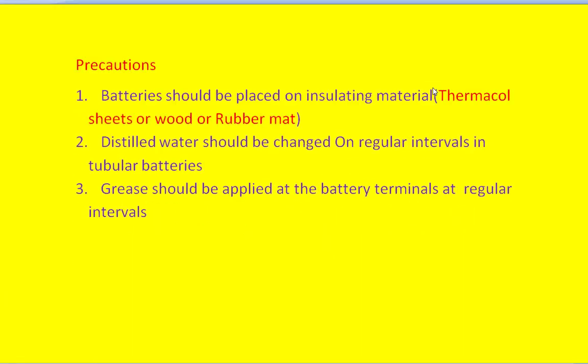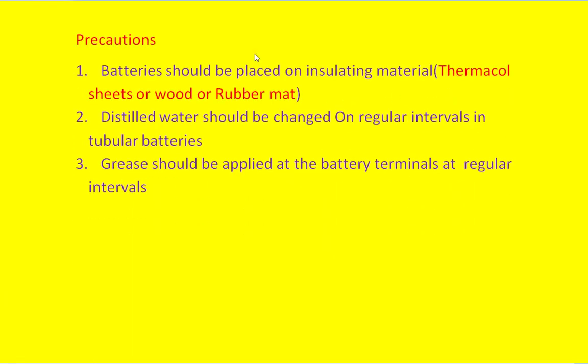Next, coming to the precautions before we connect these batteries, the batteries should be placed on insulating material, that is thermocol sheets, rubber sheets or wood. And we should maintain the distilled water at regular intervals in the tubular batteries. Similarly, grease should be applied at the battery terminals at regular intervals to have a long life of the batteries.